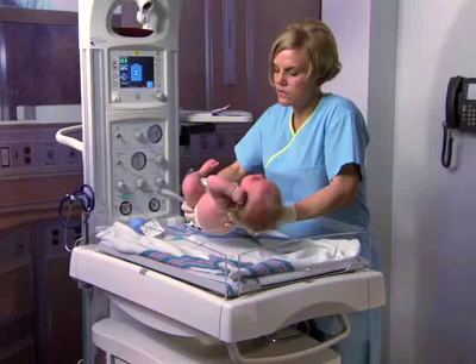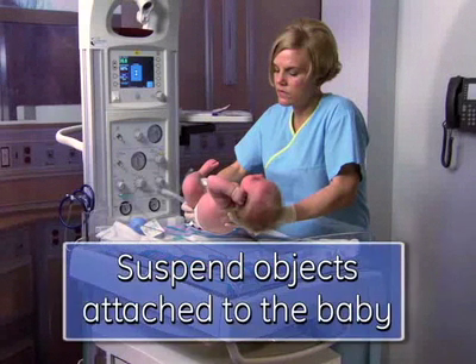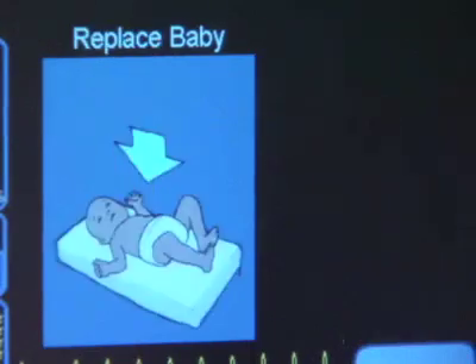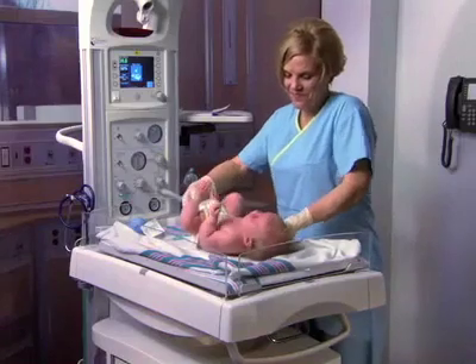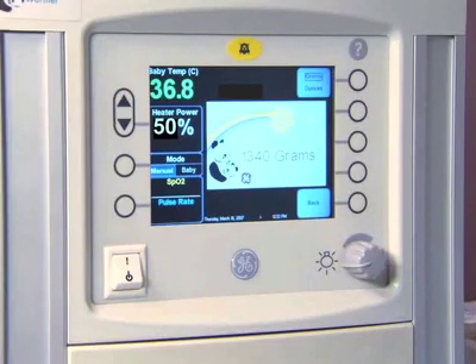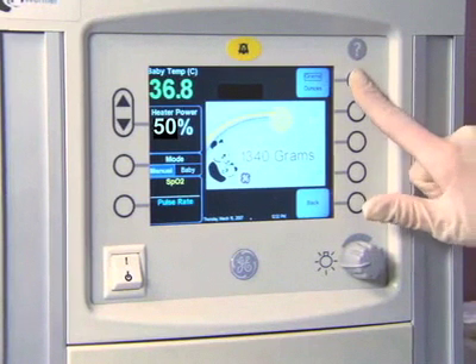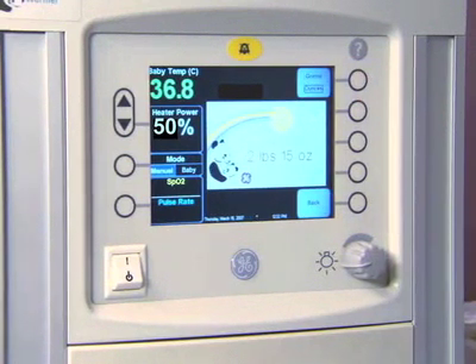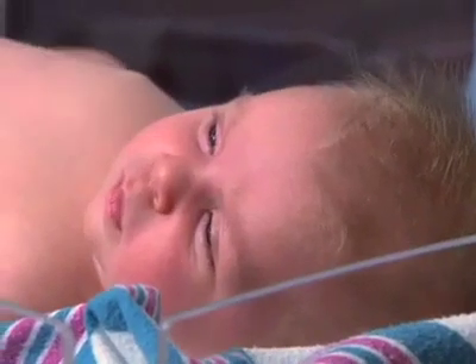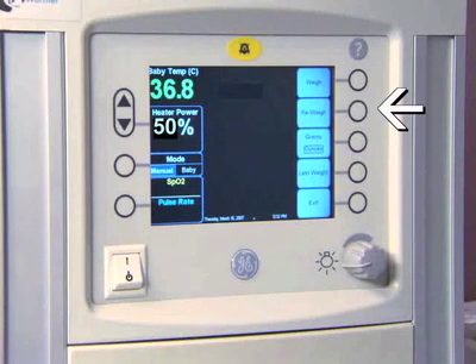Leave these objects on the bed throughout the procedure. Objects attached to the baby such as IV tubing or ventilator tubing should be suspended or held above the mattress when you replace the baby. When prompted, replace the baby on the bed, and the weight will be displayed. You may toggle from grams to ounces. After you have finished weighing the baby, two new menu choices appear. You have the option to double-check the weight using the reweigh feature. The reweigh feature allows you to verify the weight value without lifting the baby a second time.